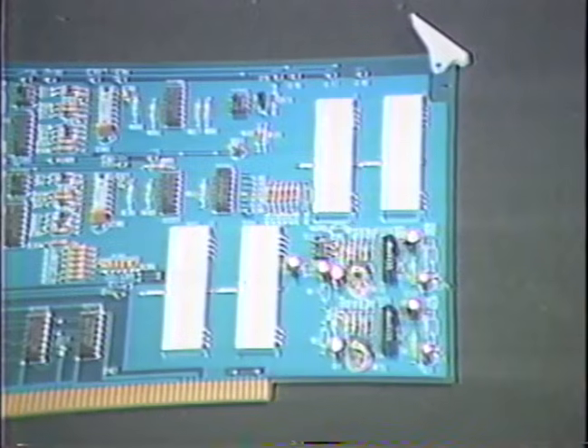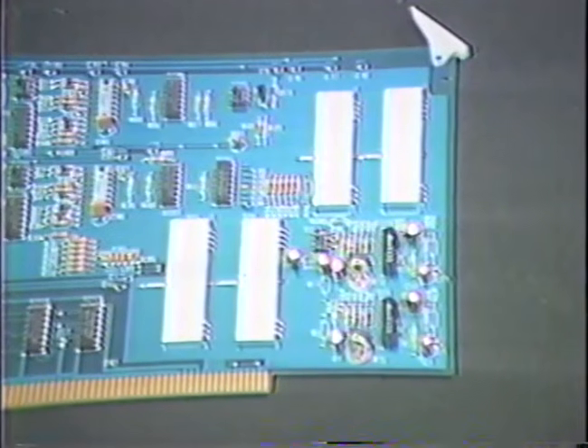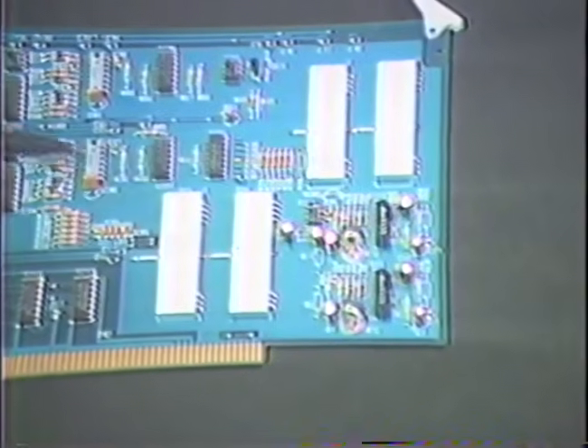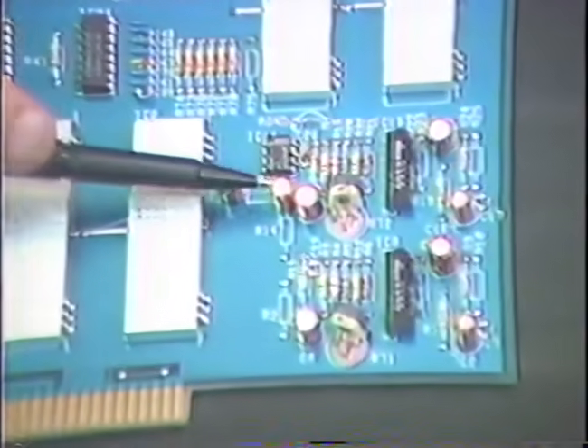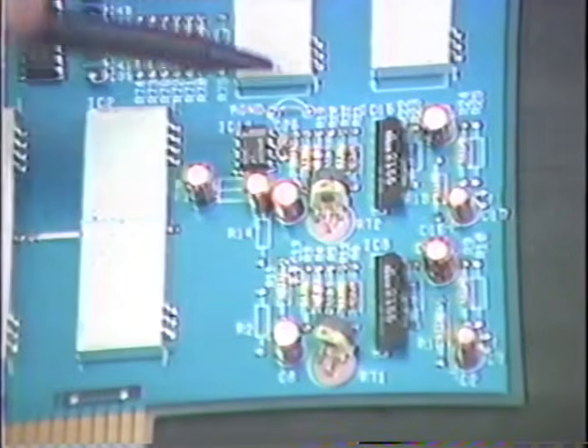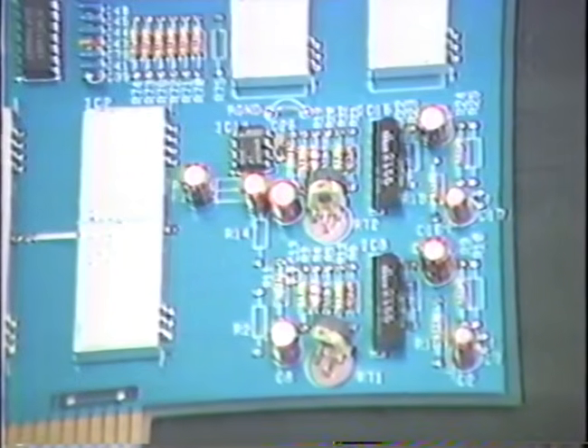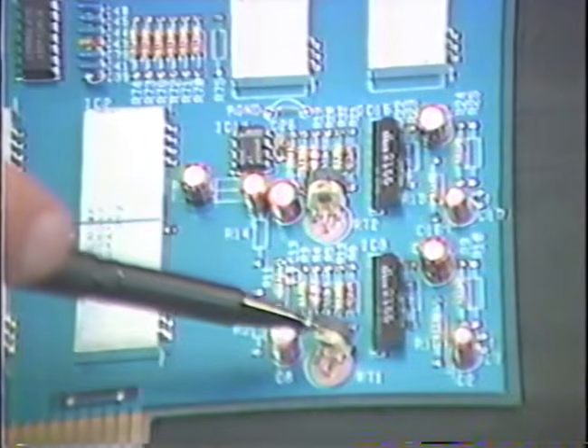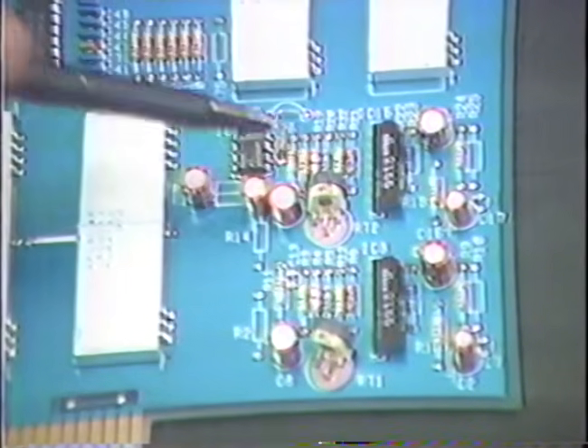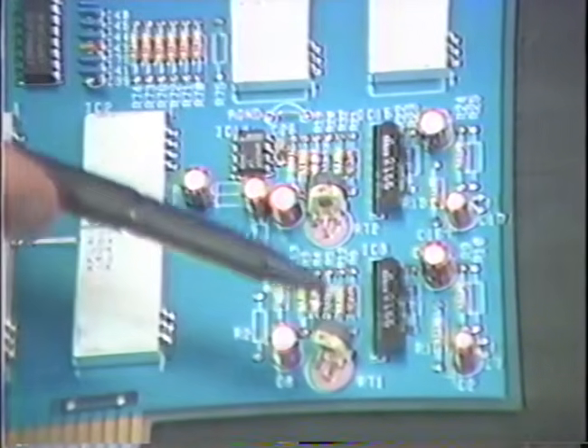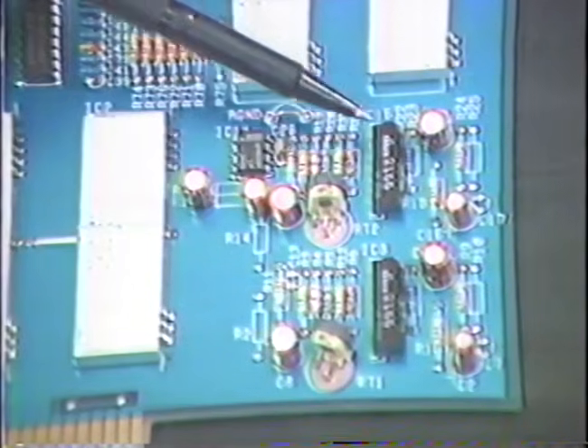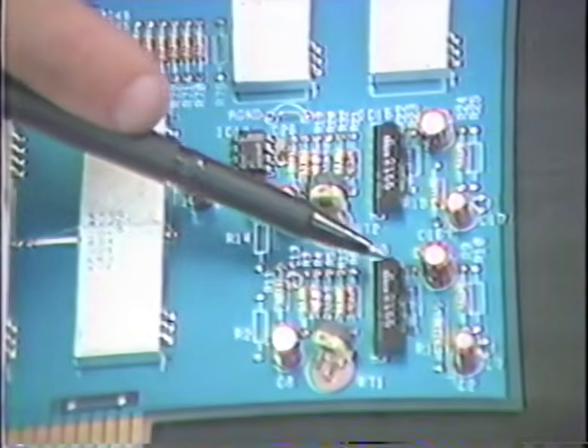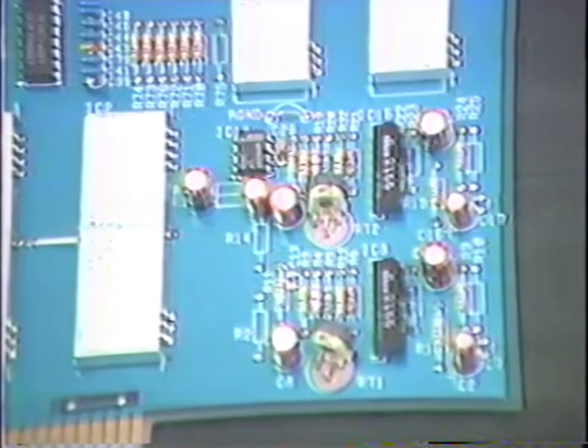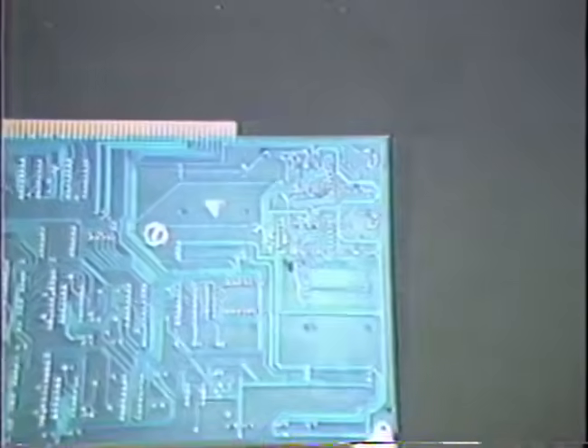The next board shows ECO number 1025 having been performed. Note the 4 new capacitors and the additional resistors. Also note that the trim pots have been replaced so that they stand perpendicular to the board. They have been slightly twisted and the DBX chips are slightly bent over, which will allow trimming to be done while the board is installed in the card cage. Also note the group of cuts and jumps on the solder side of the board.